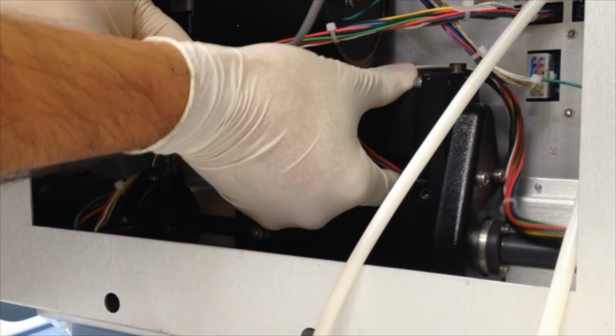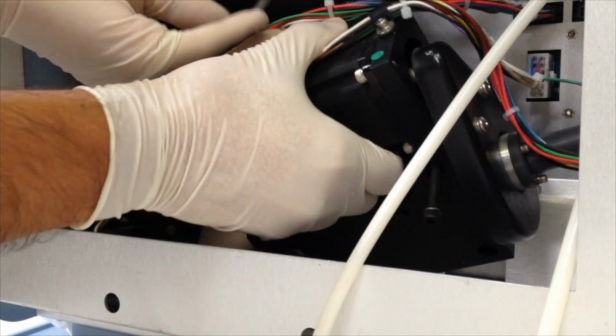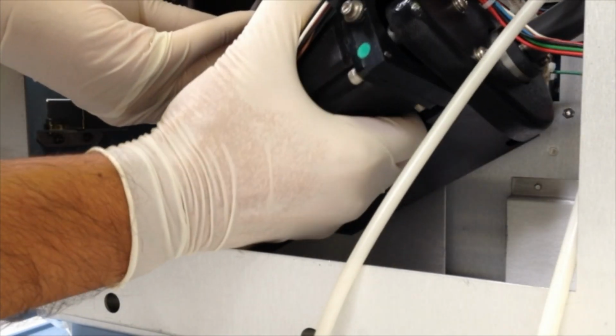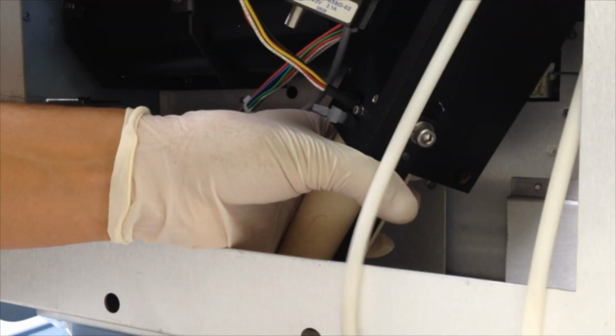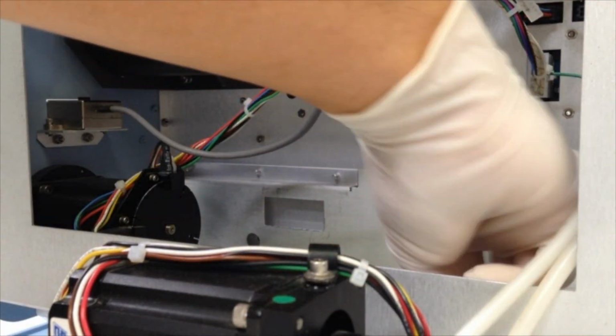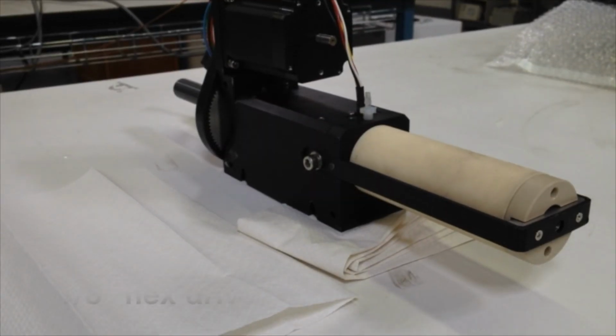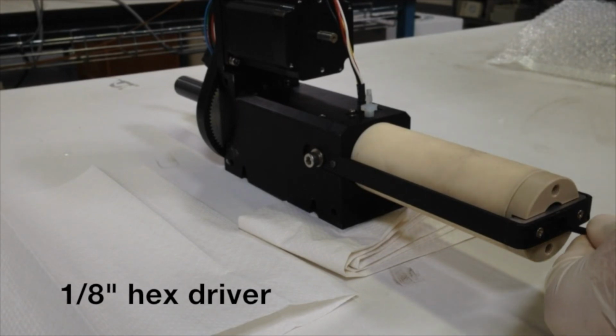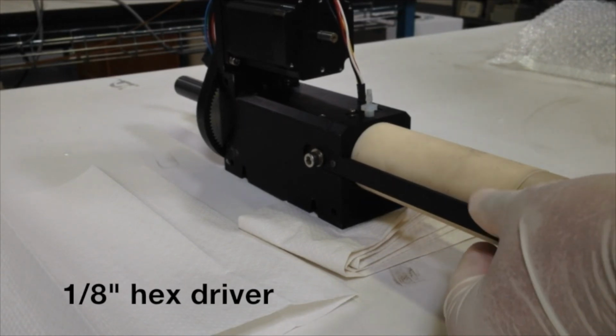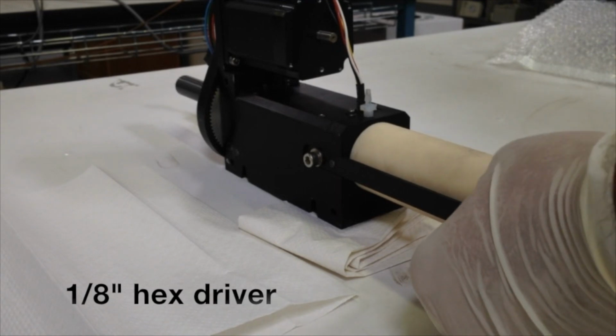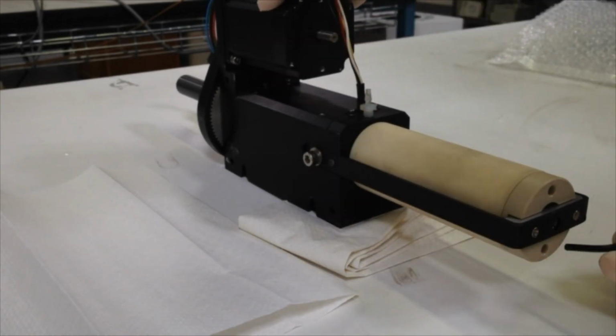For pump 1, tilt the back end up and remove the pump in a vertical position. For pump 2, tilt the back end down and remove in a vertical position. Use a 1/8 inch hex driver to loosen the set screw at the front of the pump bracket. You do not need to completely remove the set screw.